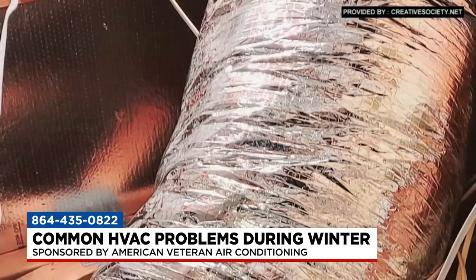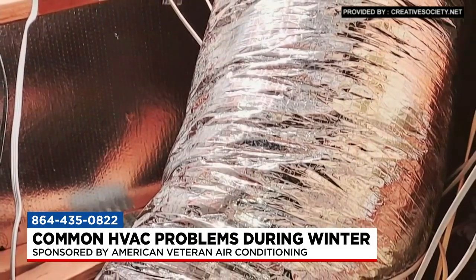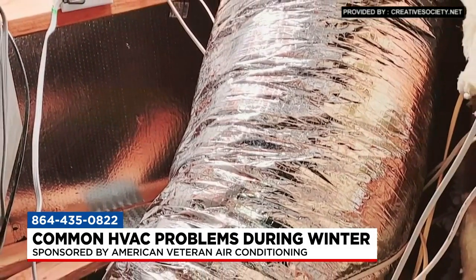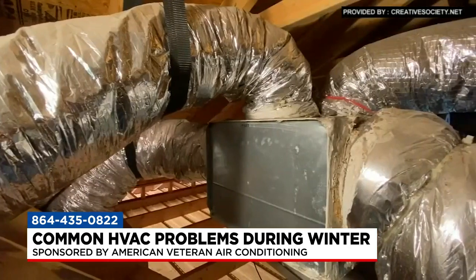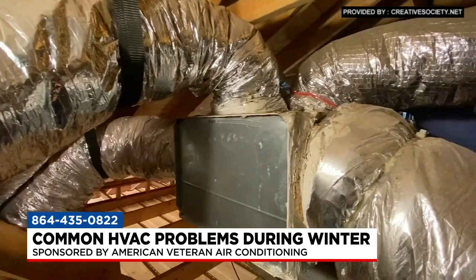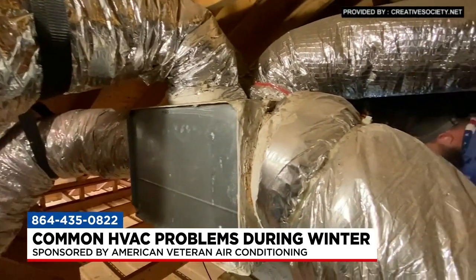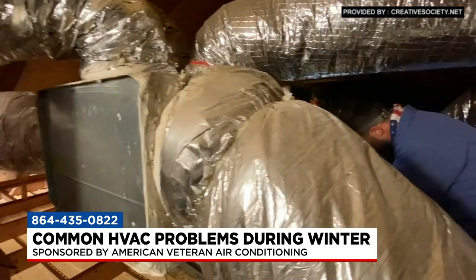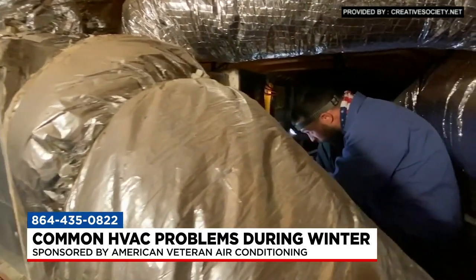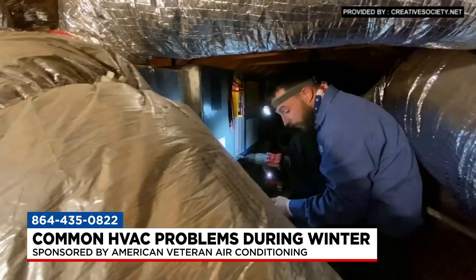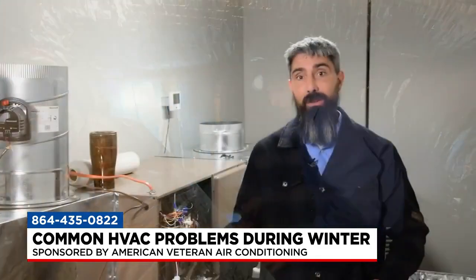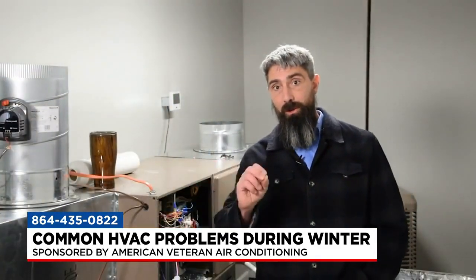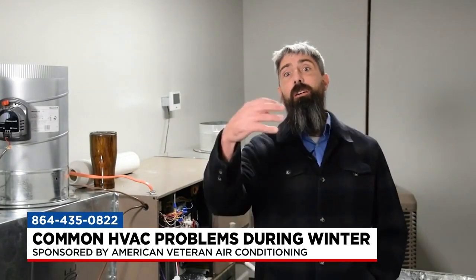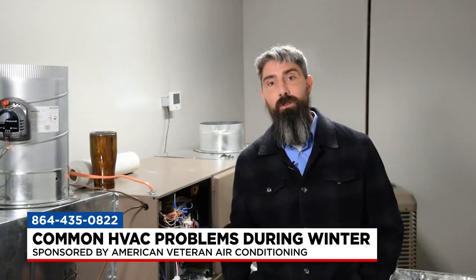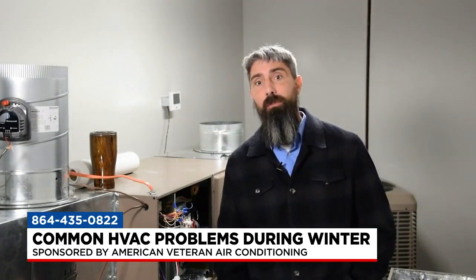On average, in new construction and most houses, it's leaking about 30% of the air in the ductwork. If it's leaking inside the unconditioned space, then by the time it gets to that last run, it just doesn't have enough air to keep that room warm or cool. It's just small pinhole leaks, but they add up across the whole duct system, so that becomes a big problem.